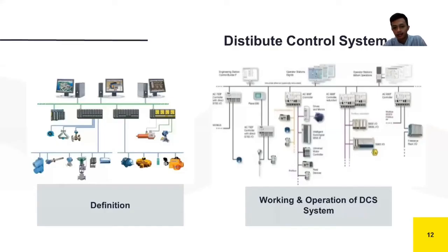And then the working and operation of the DCS system. The operation of DCS goes like this: sensors send the process information into the local I/O modules, to which actuators are also connected, so as to control the power process parameters. The information or data from this remote module is indicated in the control unit via field modules.